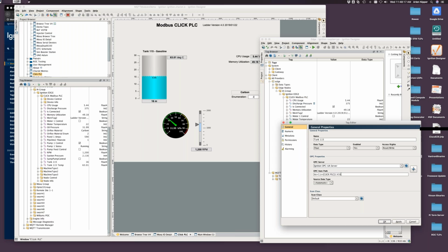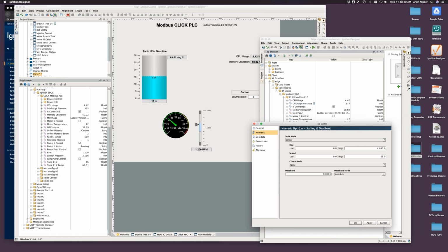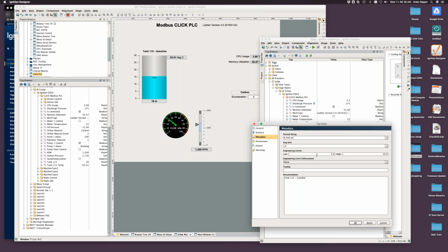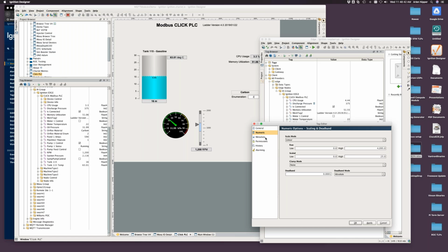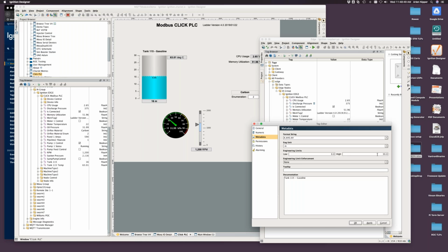I can see it is coming from my OPC polling engine as a nebulous V10, but I called it tank 115. I could go into my numeric properties and say, I'm going to scale 0 to 4095 to 0 to 25 somethings, and I'm going to call those somethings meters. So what we're going to do here is scale that 0 to 25, which I already had in there. And we're going to go 0 to 25 here.